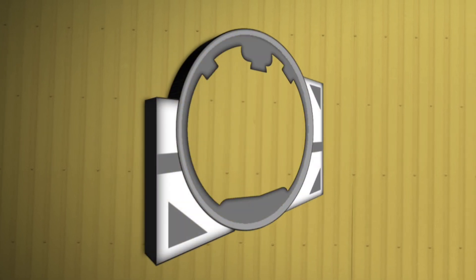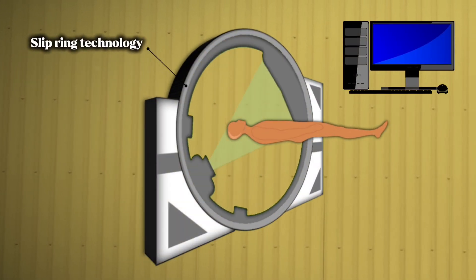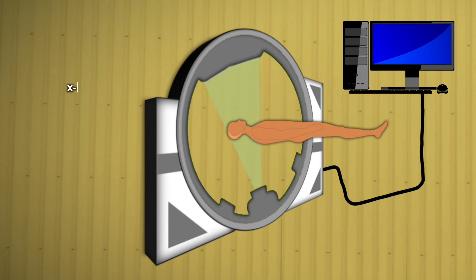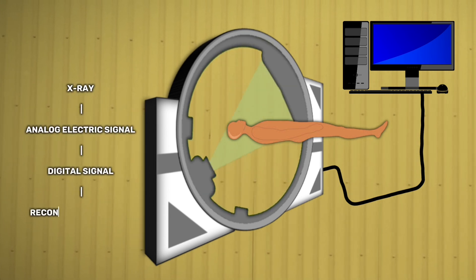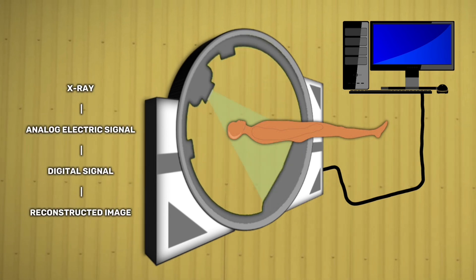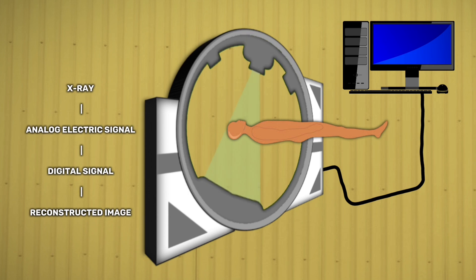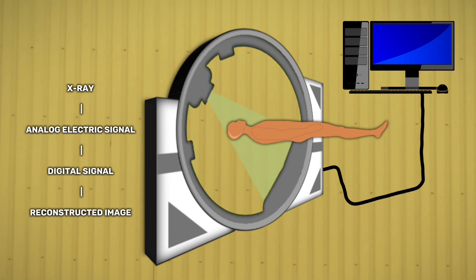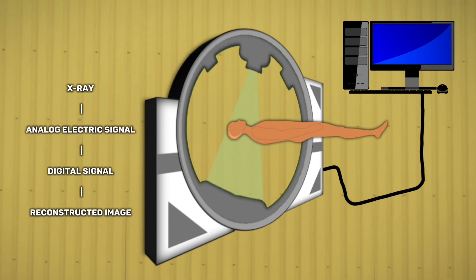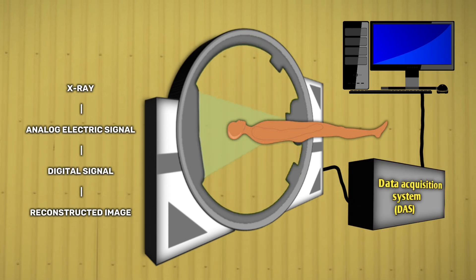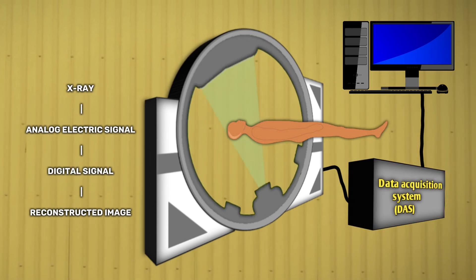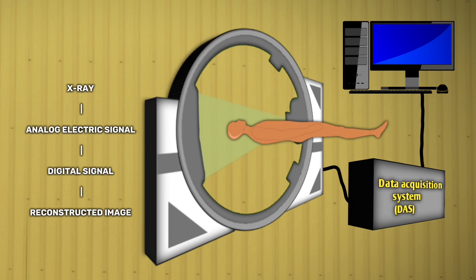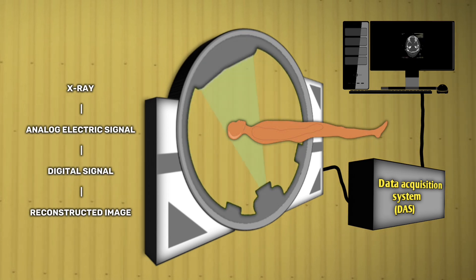When x-rays pass through the patient and reach the detectors, they convert them into electric signals. The data acquisition system receives the analog electric signals from the detectors, amplifies them, and converts them into digital data through an analog-to-digital converter.